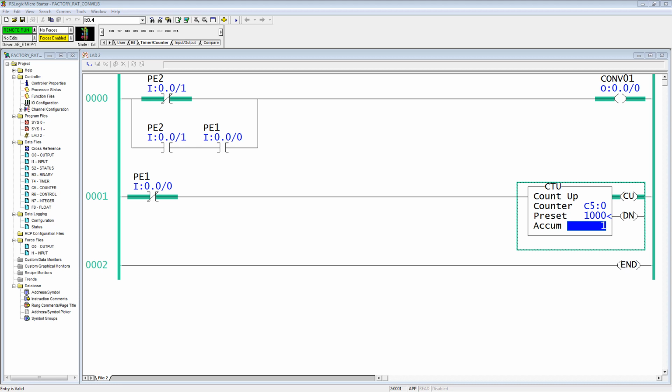We added this counter to count up specifically to tell us how many cartons are on the conveyor. So every time a carton arrives at photo I1 and then is pulled on the conveyor and clears photo I1, it gets counted in. A third one comes in, hits the leading edge of the motorized conveyor, gets pulled onto the conveyor. When it clears photo I1, it is no longer blocked and it counts up to 3. In our illustration, 3 is the limit of how many cartons that we have on the conveyor.